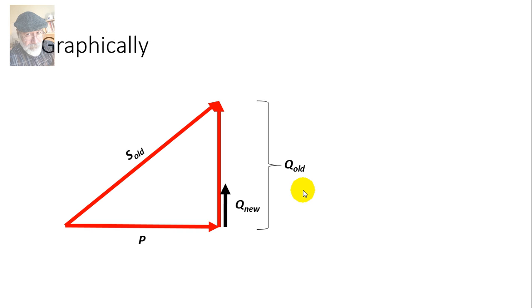But now we want the new situation to be this: this is the Q I want to supply from the utility, meaning I want the utility to see this new apparent power. Notice P hasn't changed, because the factory is still doing the same amount of work. The difference between Q old and Q new is going to be the Q supplied by the capacitor.